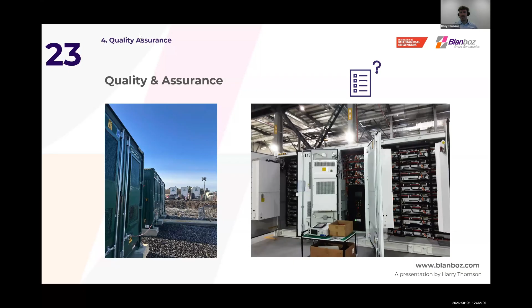So to begin with, we have factory acceptance tests. These are conducted at the manufacturer's site and are the first line to detect manufacturing defects in products. This is used to verify that the performance of the battery components, as well as the ancillary systems, such as the cooling systems, operate as expected. And this is before the equipment gets to site. A portion of these will typically be reviewed by the employer or the employer's representative.